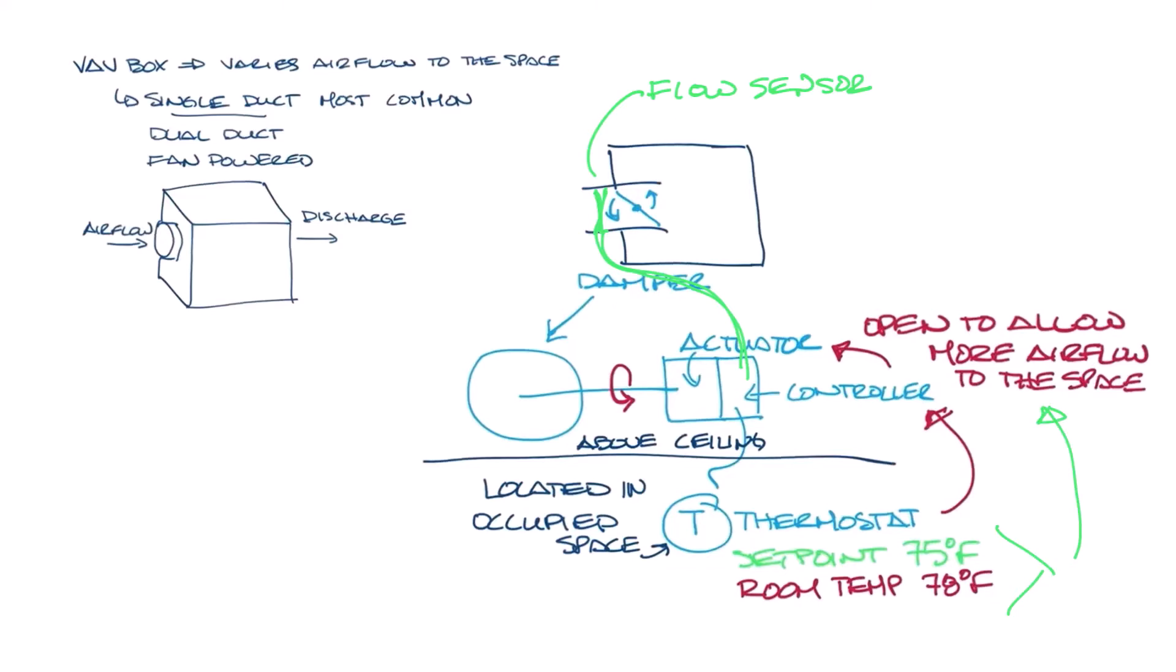The thermostat has its set point say 75 degrees and it senses the space temperature say 78 degrees and it sends that to the controller which tells the actuator open. During this whole time the flow sensor is sending a signal to the controller letting it know what the actual airflow is based on the pressures. So let's look at how the airflow sensor does this.